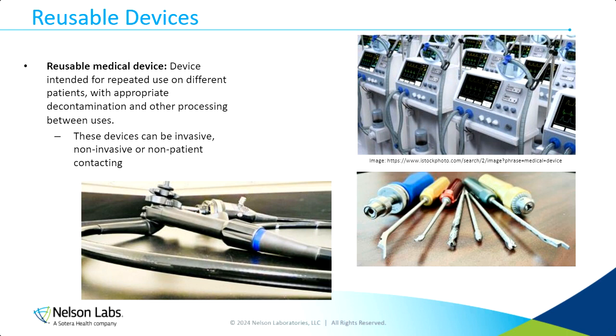The category of reusable medical device is a pretty broad category. It can include devices that are invasive, non-invasive, and even non-patient contacting devices. So devices such as surgical tools and endoscopes would be considered more of your invasive devices and are reusable in some cases. And then also devices that you may not consider a reusable device but still are, would be items like monitors or surgical lights or blood pressure cuffs, stethoscopes. These are all still considered reusable medical devices, though they may be a little bit less invasive and potentially non-patient contacting.